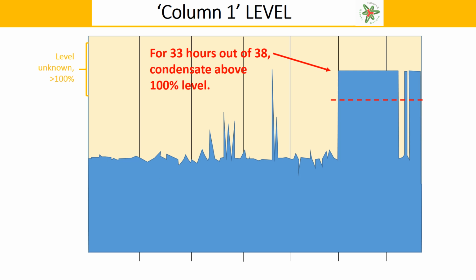Now we've gone to look at the chart to see what's happening in column 1. Here we have the column 1 level shown over a week's period. You can see that normally the condensate level is 55%. There have been a number of small disturbances in the last 7 days, a few times reaching up to 100%. In the last 38 hours, the level has jumped to 100% and stayed there for 33 of those 38 hours.